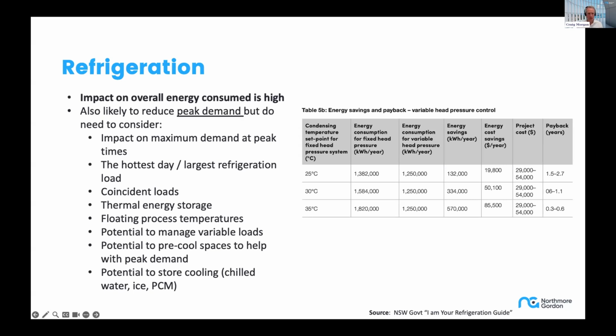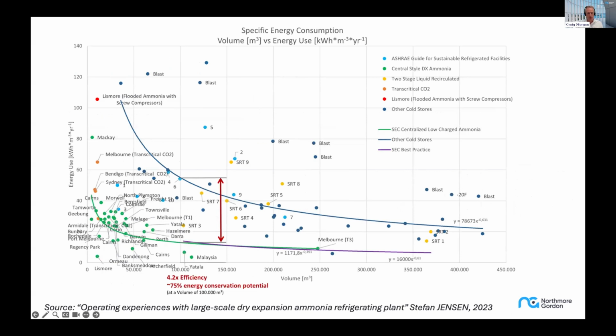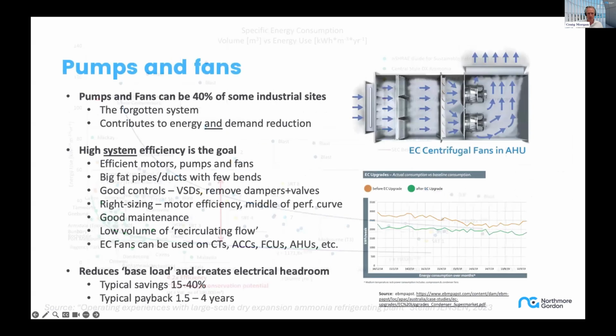Or a thermal battery or a cold battery. There are other ways to avoid peak loads by floating process temperatures, cool store temperatures, either down or up. So pre-cool if you know you've got a peak coming up. Managing variable loads, and I've already talked about sort of cold storage. This is just another set of data that reinforces how efficiency in systems varies substantially. You can see the source there, you'll get the slides. I'd recommend you go and have a look at that. There's a lot of work being done on mapping the efficiency of systems.